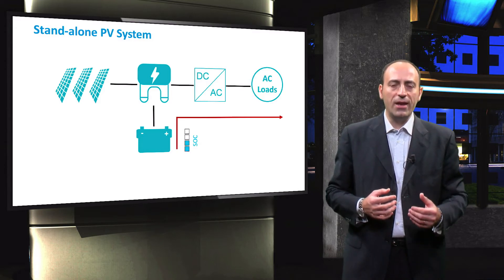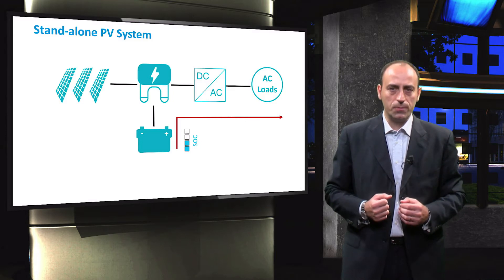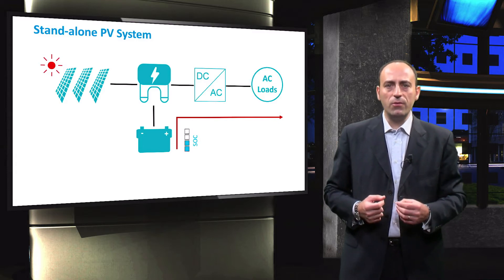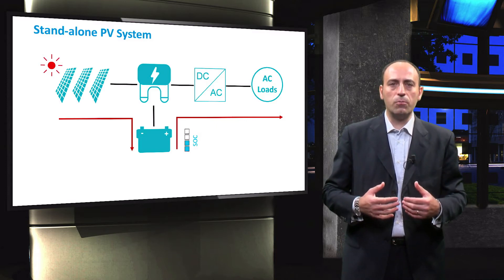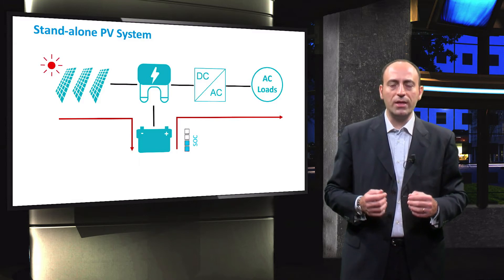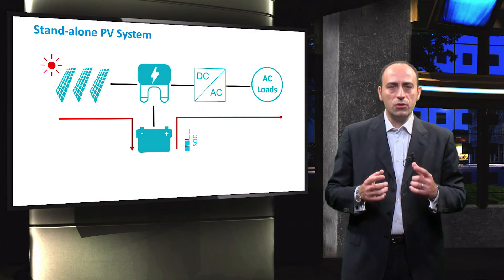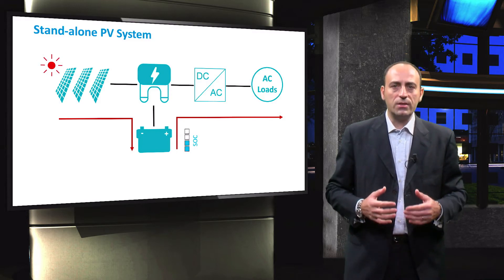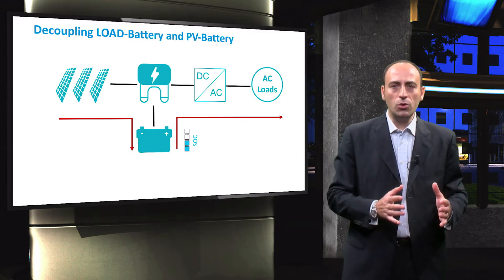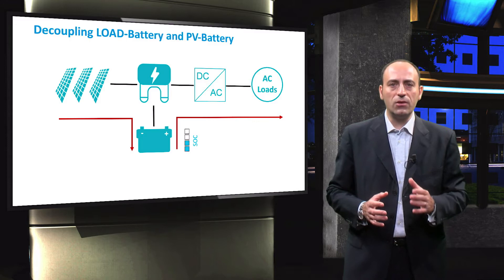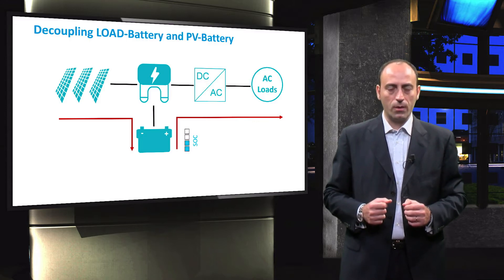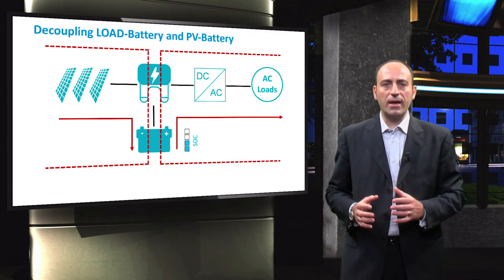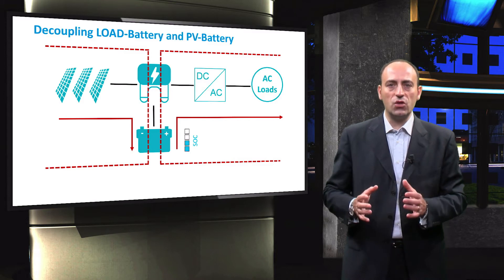The battery will supply energy to the load while its state of charge starts to reduce. Later, when the sun is available, the PV module begins to deliver electricity. This energy is sent to the batteries for recharging them. Now the battery is supplying energy to the loads and receiving energy from the PV modules at the same time. The whole idea of this animation is to make you understand that energy flow in the standalone PV system happens via the batteries at all times. To design such a system, it is important to decouple the PV module and the loads from each other and instead connect them separately to the battery through the charge controller. By following such a design approach, we can split the system into the load-battery bank combination and the PV-battery bank combination, thus making it easier to analyze and size the different components.